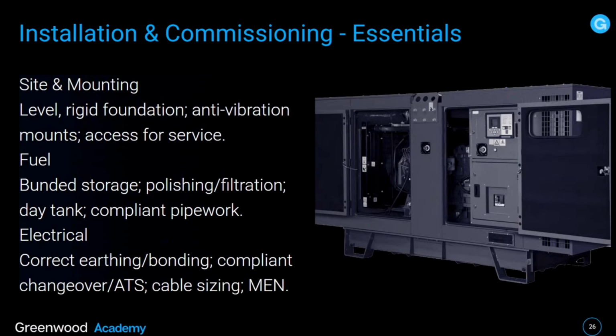Now, site and mounting. You must level the site. You need a rigid foundation, anti-vibration mounts, and access for service. This is really important when you're positioning or locating a genset, to allow for adequate access when it comes to maintenance and service of the unit, which is required because we're talking about moving parts, so there's a lot of things that need to be maintained.